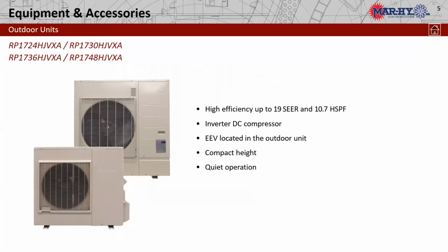Okay, so we have 4 units available. We have the 2, 2.5, 3, and 4 ton. This is a high efficiency piece of equipment, up to 19 SEER and an HSPF of up to 10.7. That's pretty good. It's the inverter DC compressor that's digitally commutated. So the EEV will be located in the outdoor unit. It's very similar to the same type of installation we would do with our mini splits. With the EEV being located in the outdoor unit, it's got a compact height and a very quiet operation.